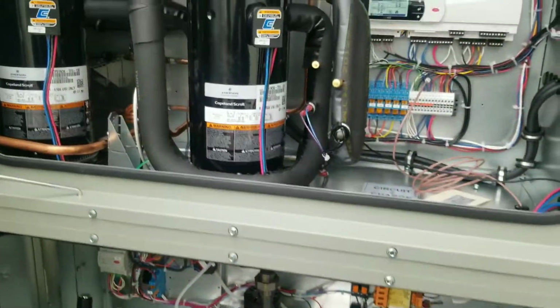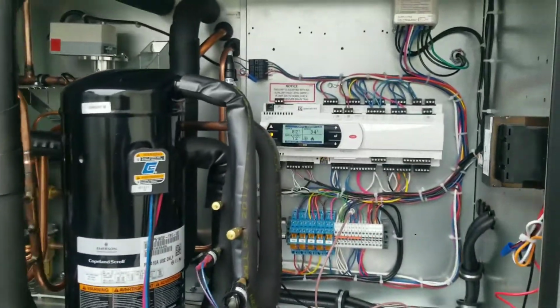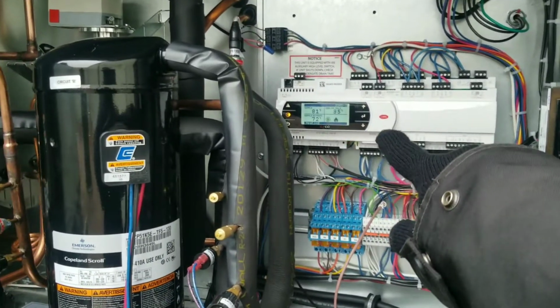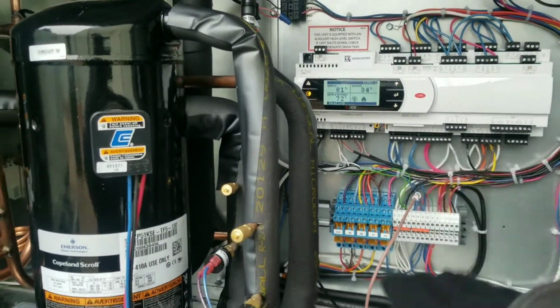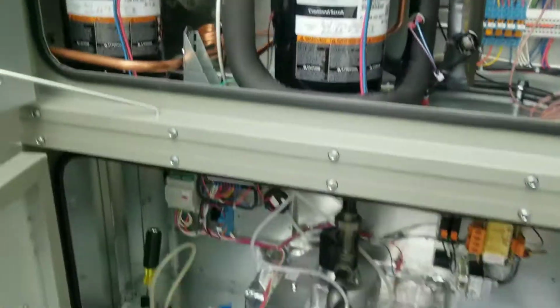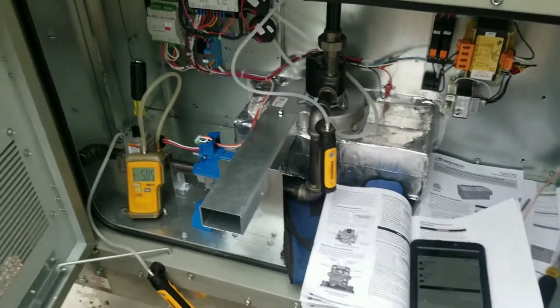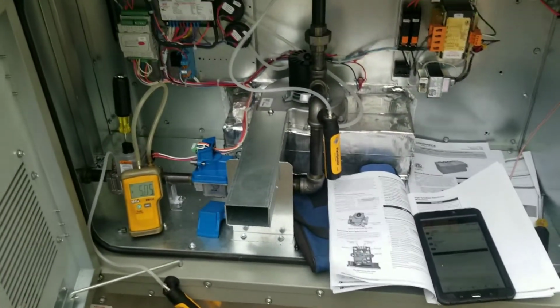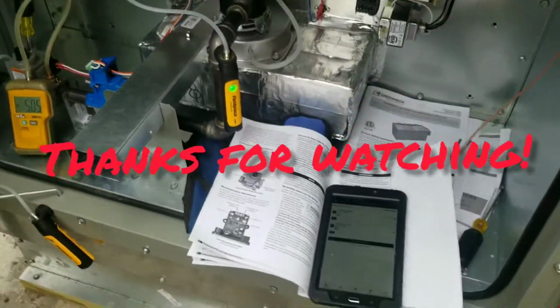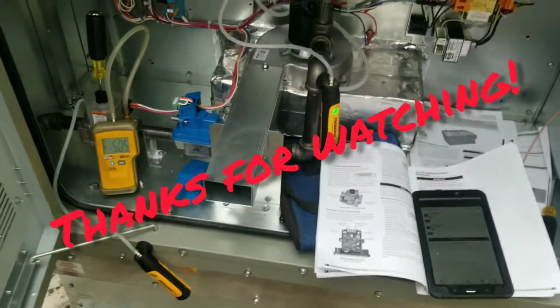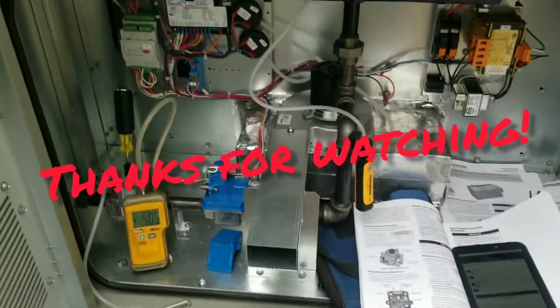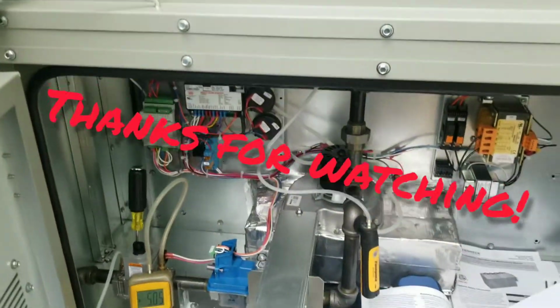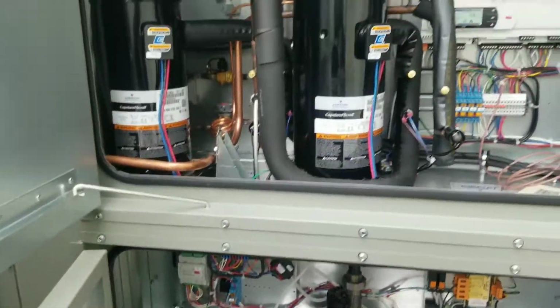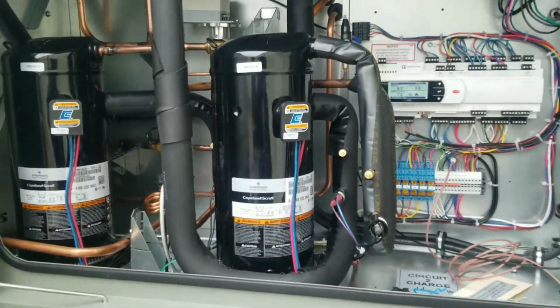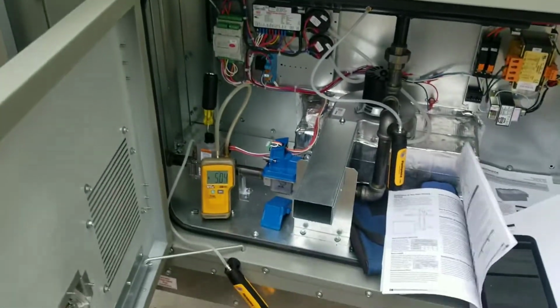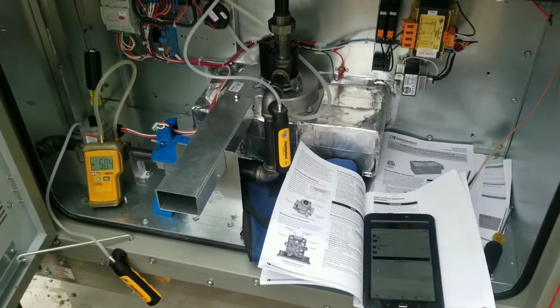We're gonna watch it for a few more minutes. You can see my supply temp is dropping now as the gas pressure drops, so it'll find a happy point there and try to maintain that 72. So we're gonna call this guy good. We'll watch it for a little bit longer, make sure everything else looks okay and continues to modulate like it's supposed to. So let me know what y'all think. Maybe we'll get some video on the cooling startup when we get to that point, but for right now they got heat. We're gonna call it good.